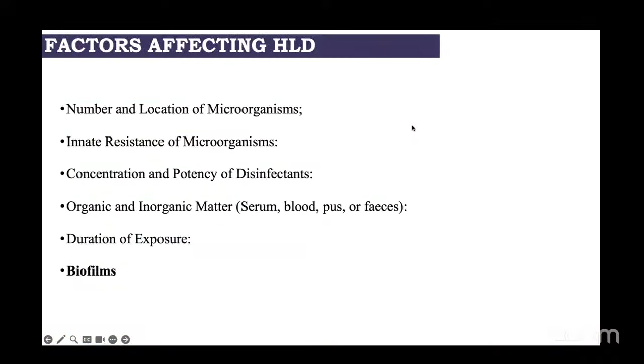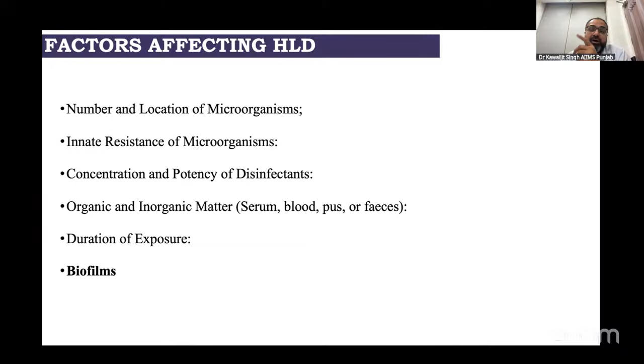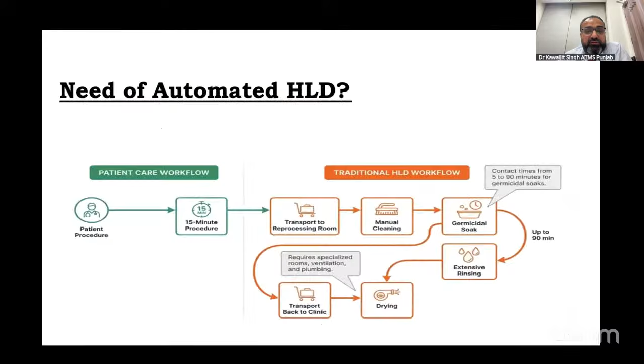I'll just go through. Now, certain factors affect high-level disinfection. These are the number and location of microorganisms, resistance, concentration and potency, organic matter exposure, and biofilm. Biofilm is a very important cause of HLD failure because the chemicals cannot penetrate the mature biofilm. Hence, adequate drying of the scopes is required.